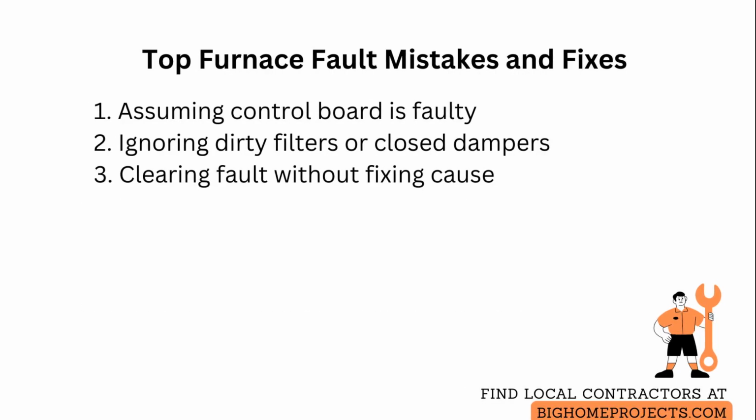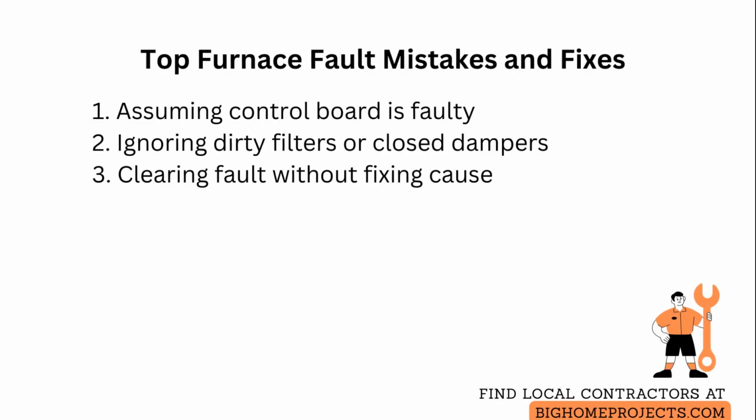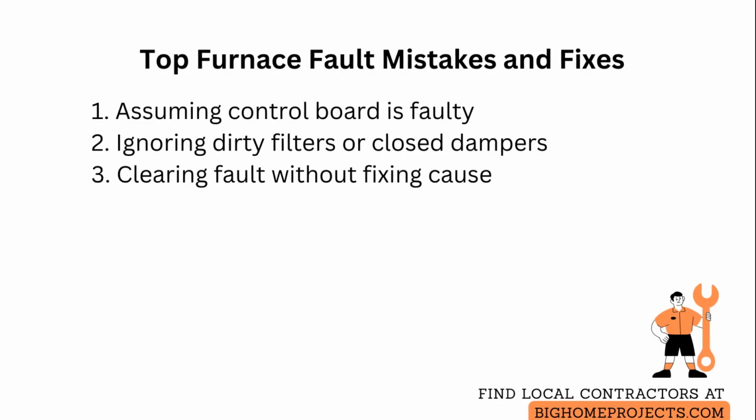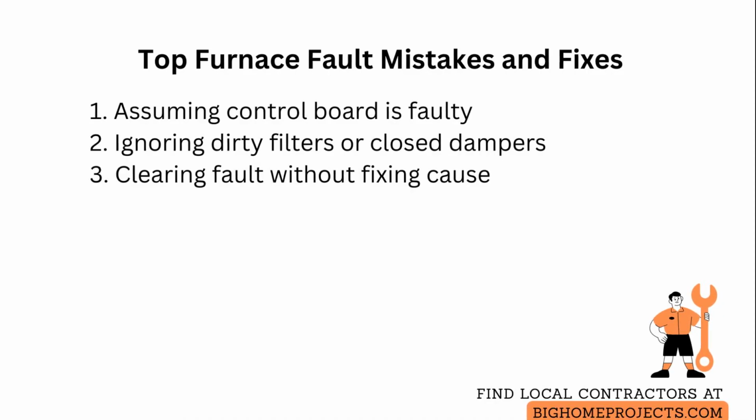Common mistakes include assuming the running blower means the control board is faulty, which often leads to unnecessary replacement. Verify limits and airflow first and only replace the board after eliminating other causes.